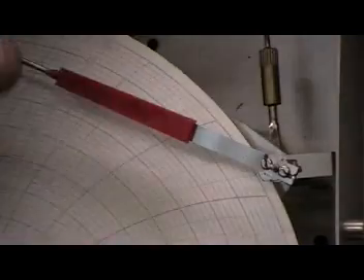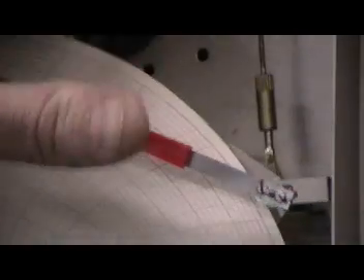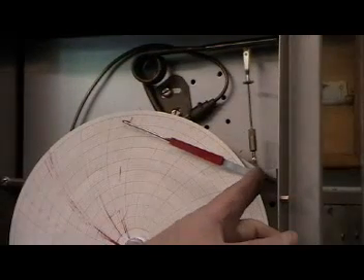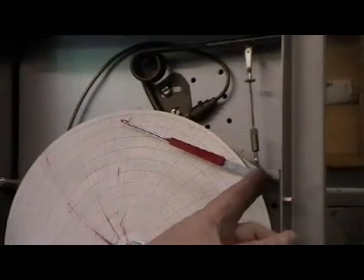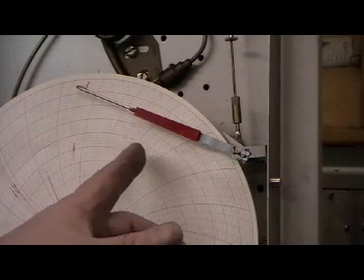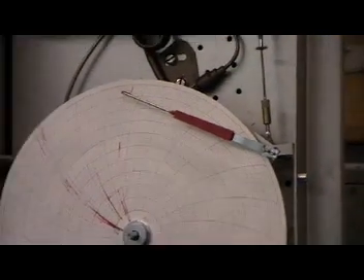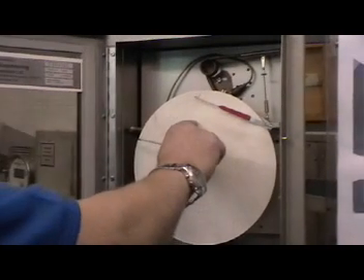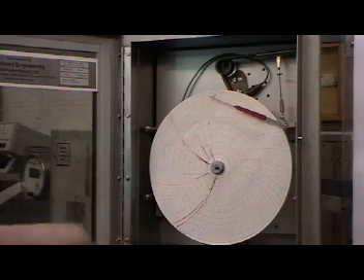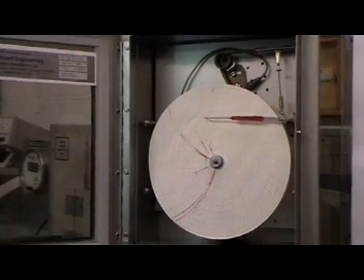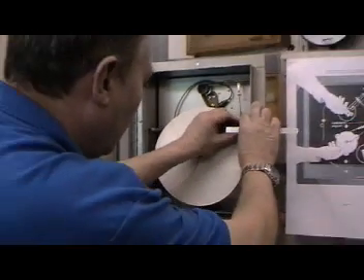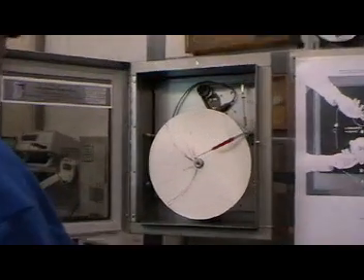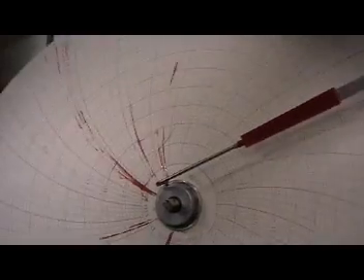So, if it's not possible to get the span that you require on the fine span, then by moving the pivot point closer to the center pivot increases the movement. Moving it away decreases the movement. So, we're now going to quickly show with the 2500 we were reading 2600. As I already know exactly where this instrument falls in to be calibrated, I'm going to drop the pen on, drop the pressure off, re-zero it.